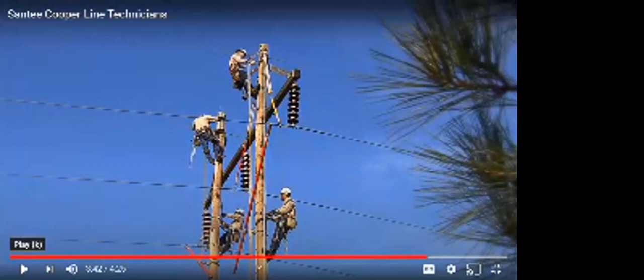This gives a good example right here. This is energized, 115,000 volts. But the clearance away from the pole to where the conductor is, is sufficient for them to climb in between it. What are they using to hold the conductor up and push it away from the pole? Using those fiberglass sticks you were talking about. Yep, see, he's got a fiberglass stick pushing it away, and this one here is to hold it up.